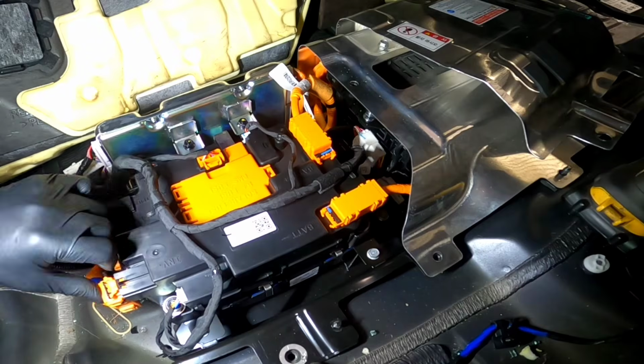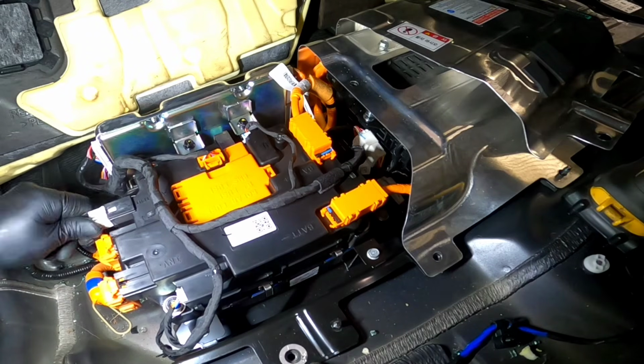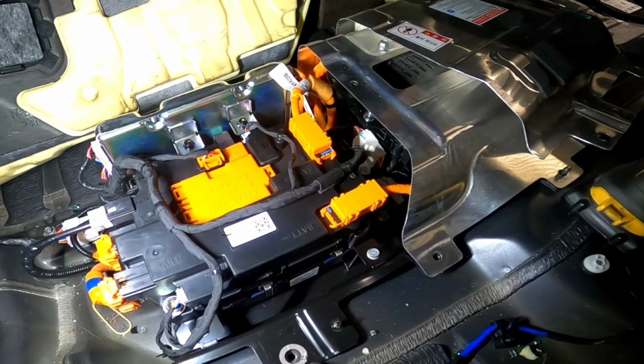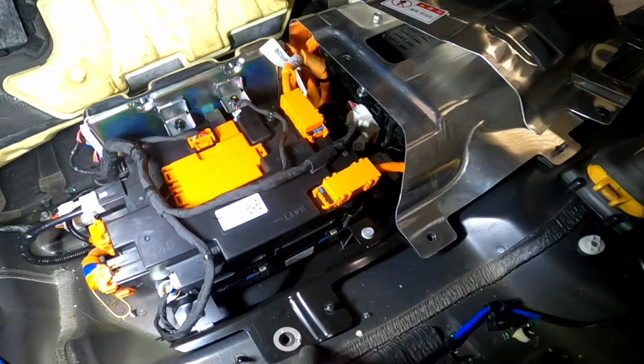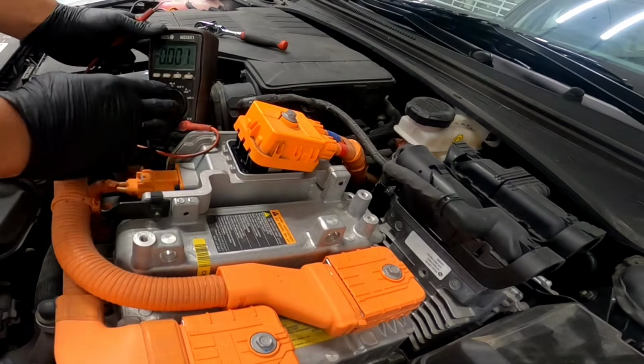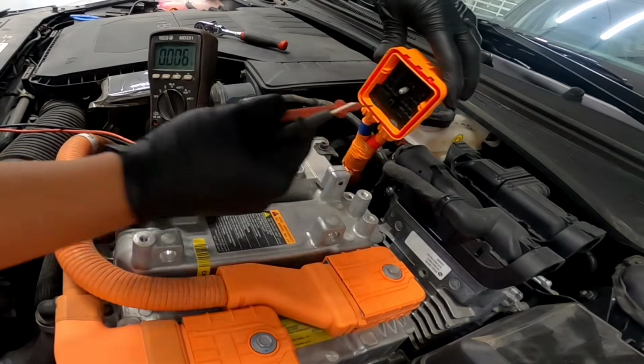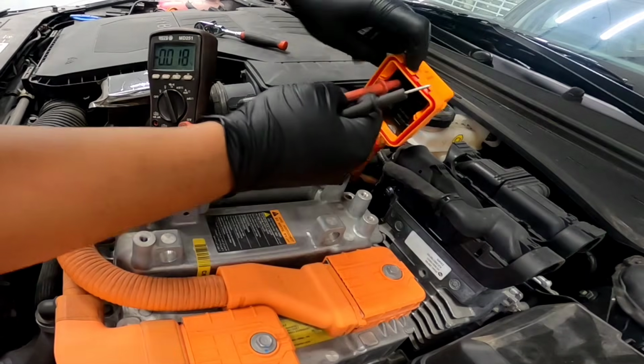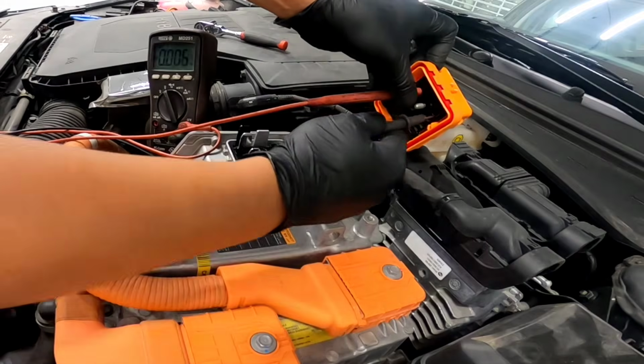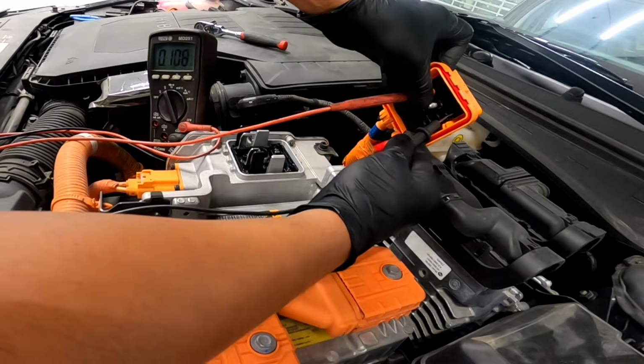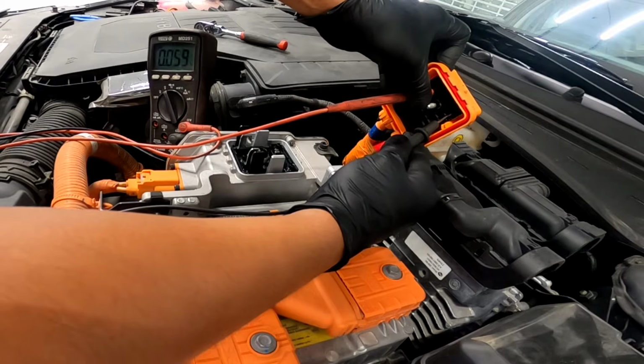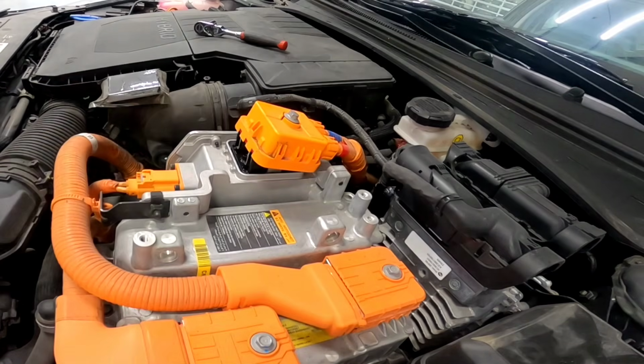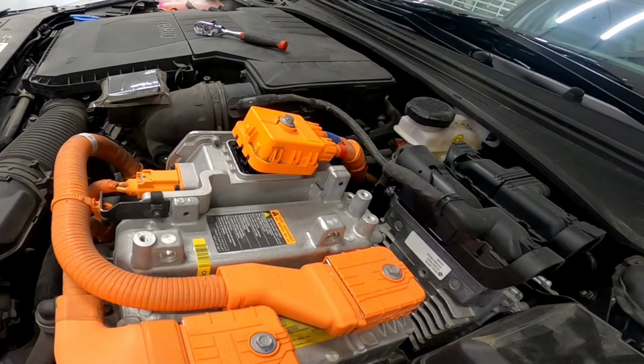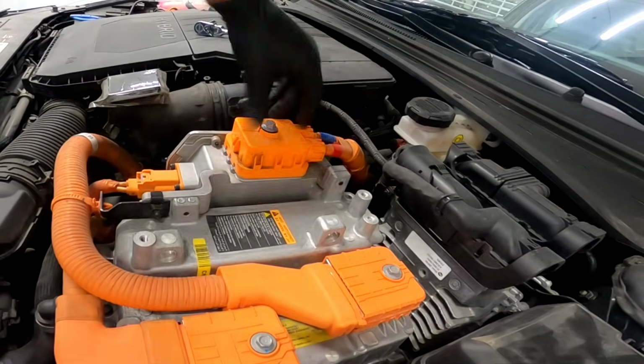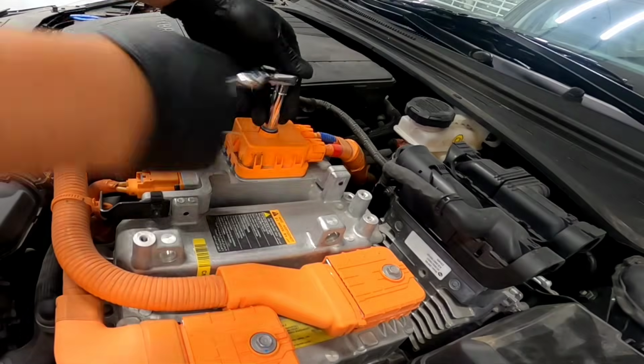I showed you earlier that it should have 0 volts, right? So now everything is connected. We should expect 0 volts on our high voltage cable there on the front, right? So here's our meter again. Let's say we don't have any problem with the relay. So I'm going to probe the front. As you can see, there is 0 volts there, right? 0.1. Earlier it was 225. Okay, so that's good. So I know I'm safe. There's no voltage coming out there. So just start this at 8.7 foot-pounds.